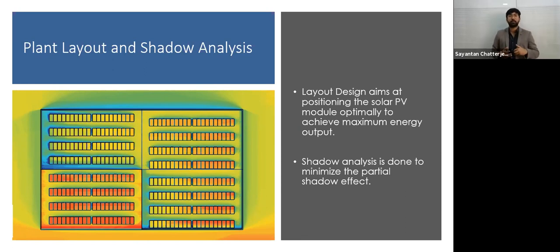But in the section on the north side, where you see some yellow color and bluish shadow, there is a moving shadow. If we connect the solar modules in series, suppose 18 modules in series connection, and there is a moving shadow on one or two modules, the total string will be affected. Shadow on one module means the total 18 modules' generation will be hampered, and eventually there will be a hotspot and the module will get damaged.